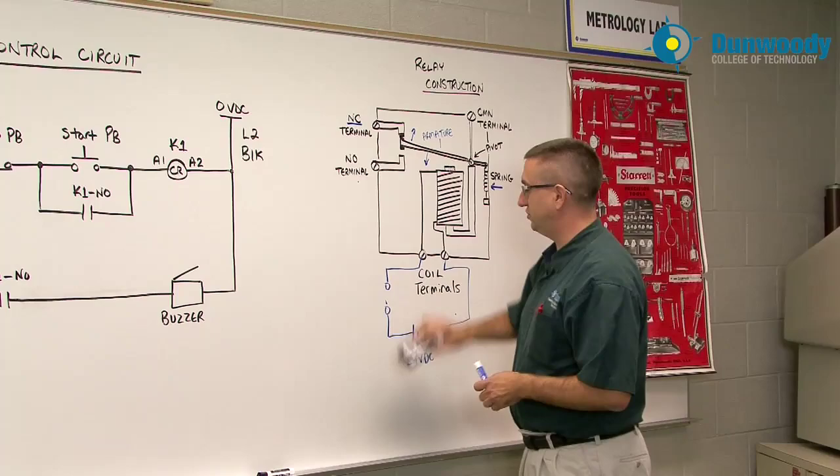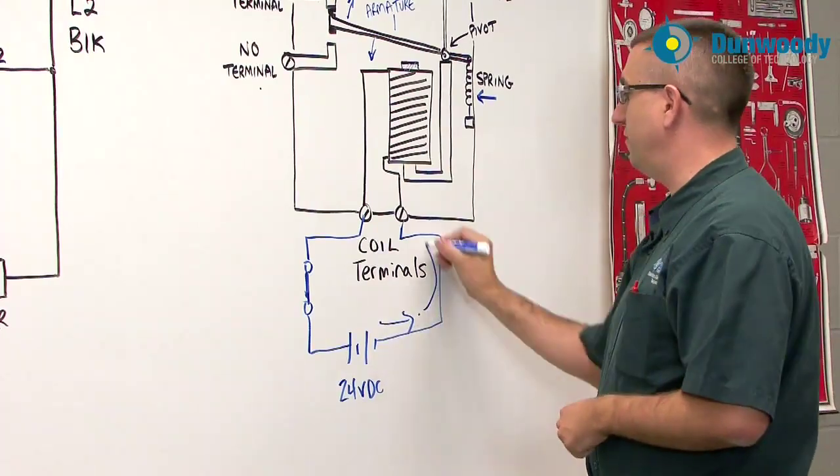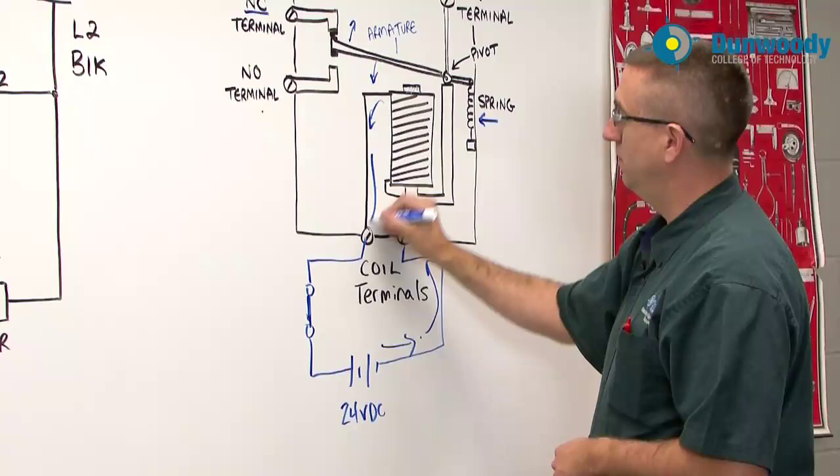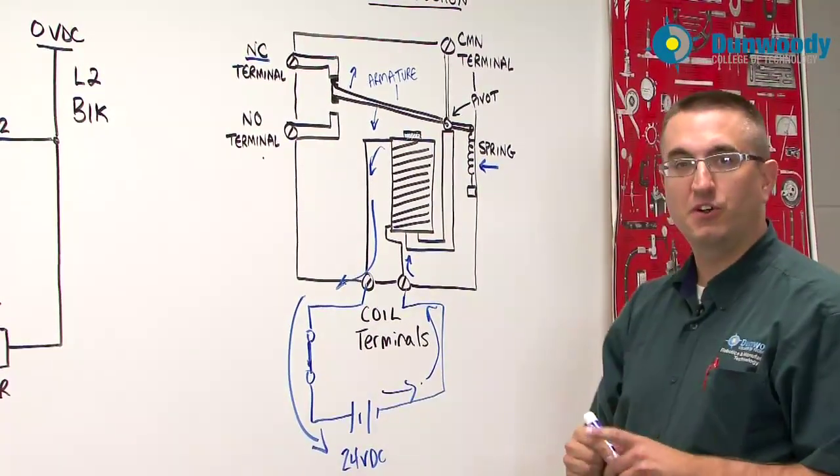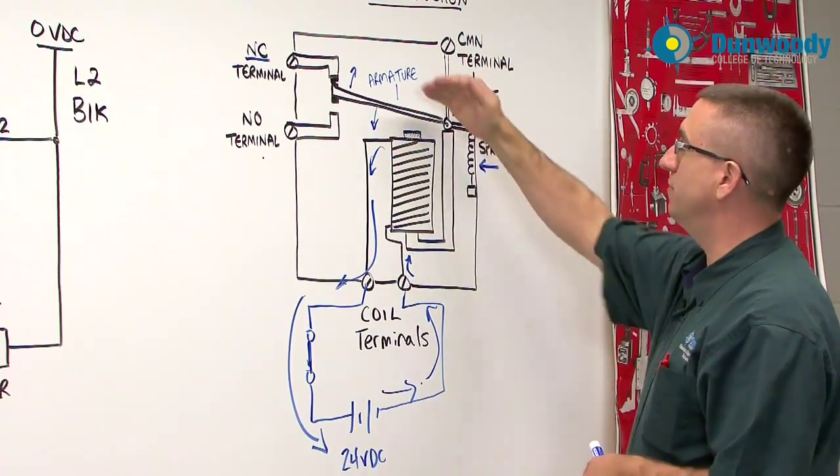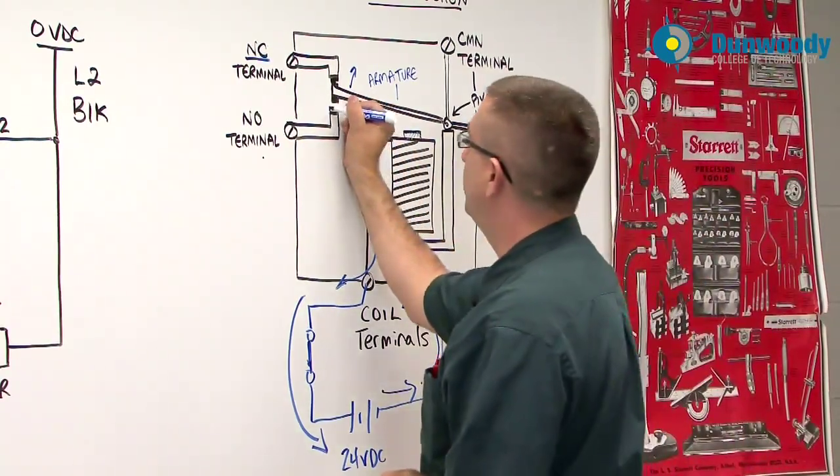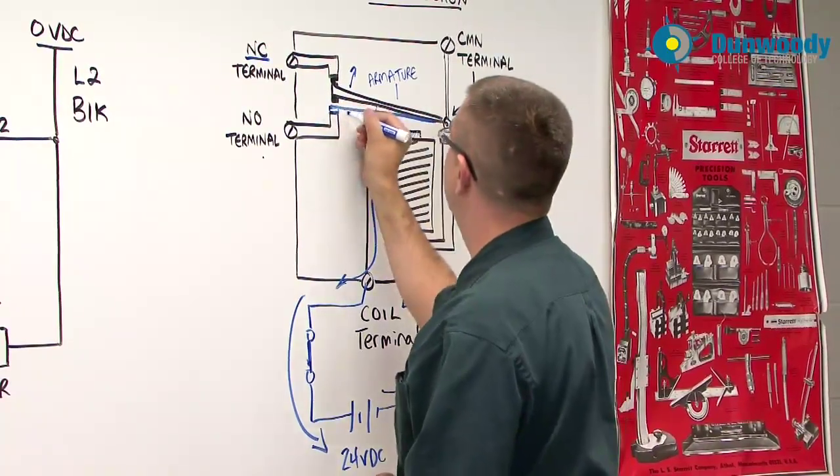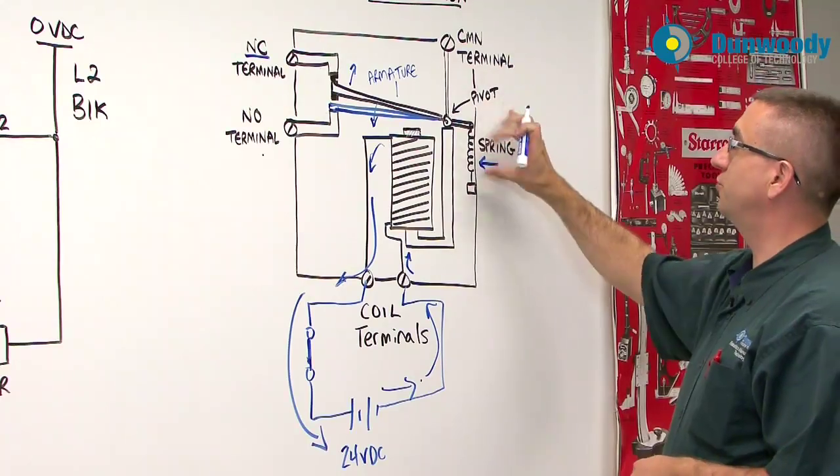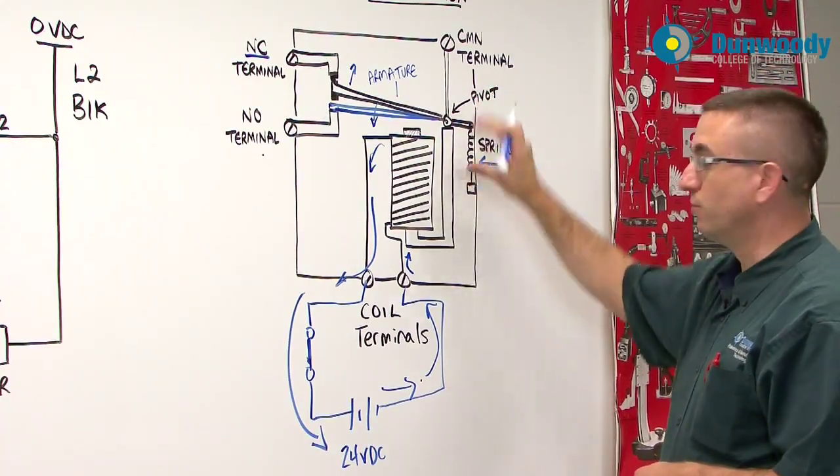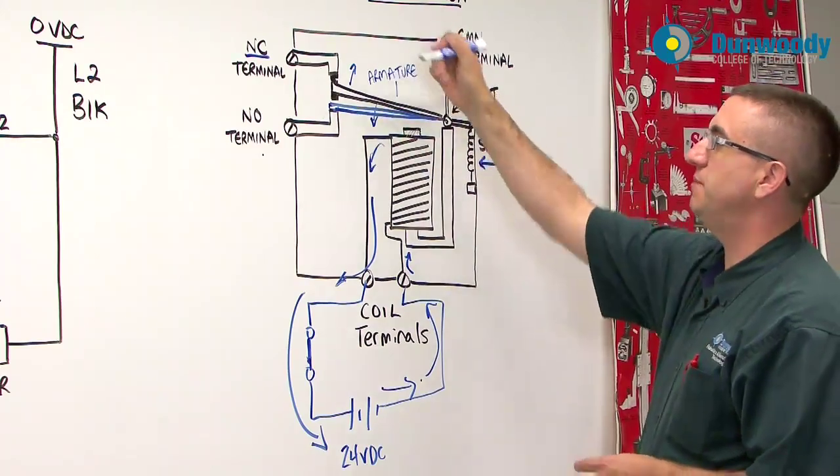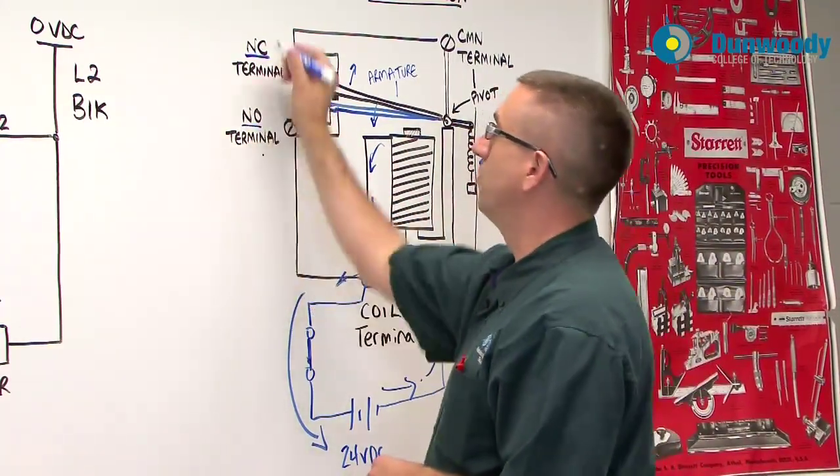As soon as I energize this, if I was to close this switch, now I have current flow. So the switch is closed and I'm going to get current flow up and through my coil and back to the source. As soon as there is current flow this becomes an electromagnet. At that point the armature is pulled down and now I'm going to go down to the normally open contact. So we'll use blue to represent that. But the armature would change states and it would now be sitting down here, and it would be pulling on the spring a little bit. So the second that I release this energy or open this switch, the magnet goes away and the spring pulls back on it and takes it back up.